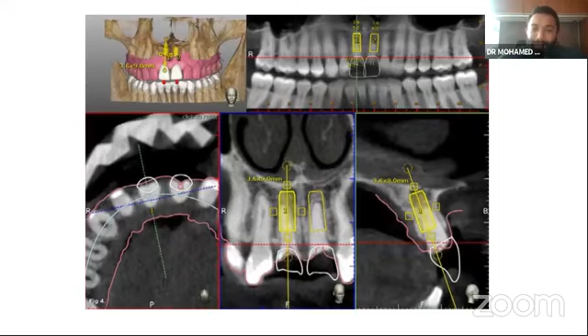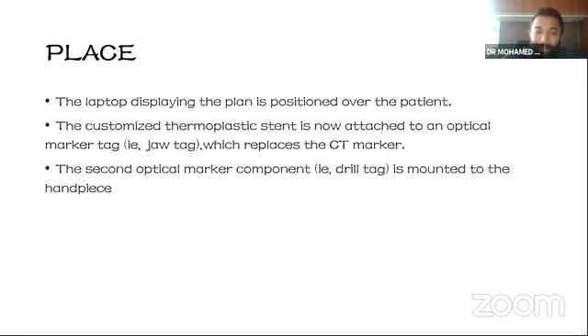Then comes placement of the implant. The laptop displaying the plan is positioned over the patient, and the customized thermoplastic stent is now attached to an optical marker tag. That is a jaw tag, which replaces the CT marker. We will remove the CT markers and attach the jaw tag. The second optical marker component is mounted to the handpiece. The motion of the handpiece is tracked against the patient position.